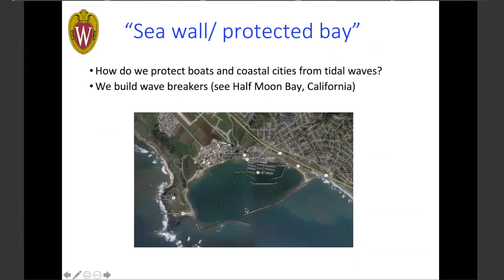And so the shoreline here would not be affected. So if you think of the valve mechanism, the valve is functioning like this shoreline without a breaker. And every pulse pressure, whether through coughing or any kind of pulsations or cardiac pulsations, is going to drive fluid into the shunt system and drain the brain out. Whereas if you develop a valve that has some kind of a breaker in it, you will be better off.